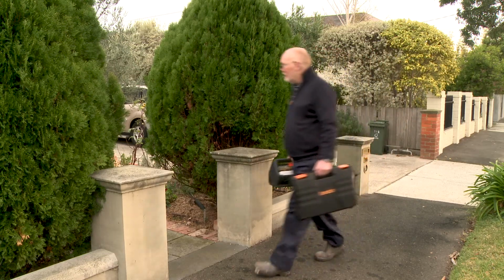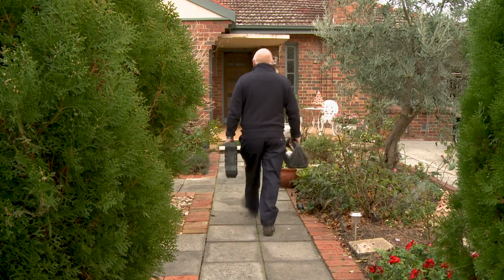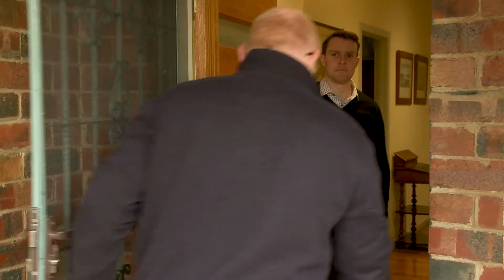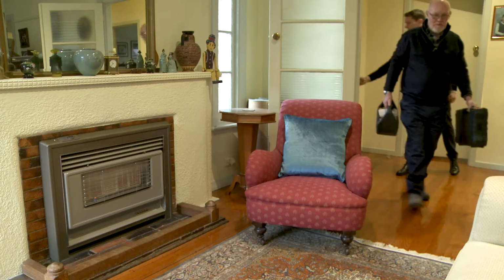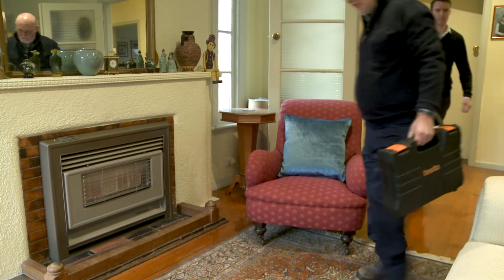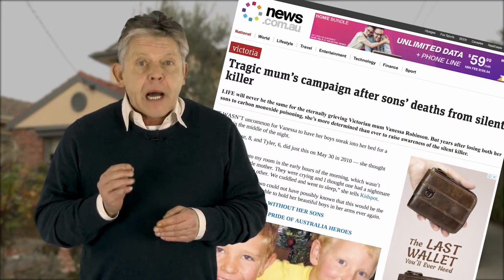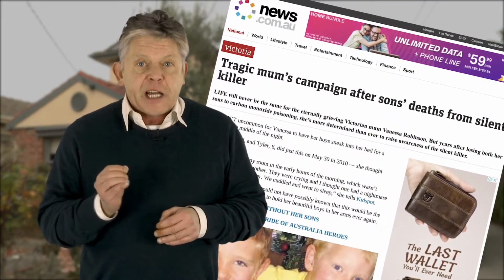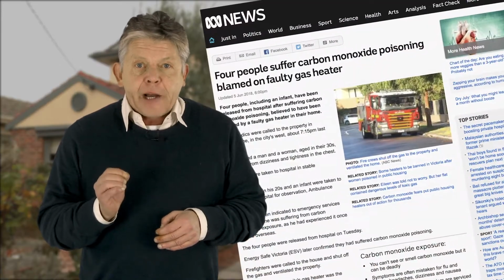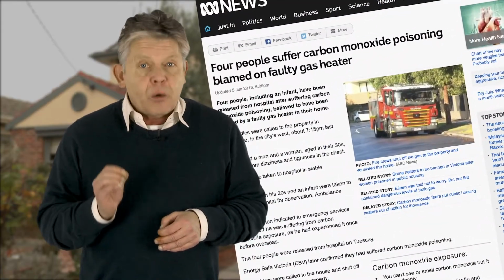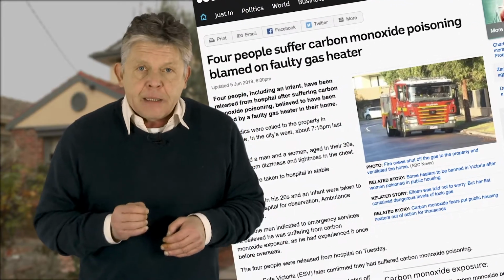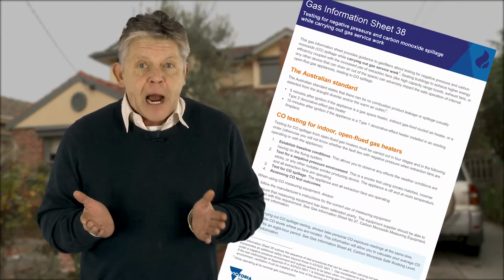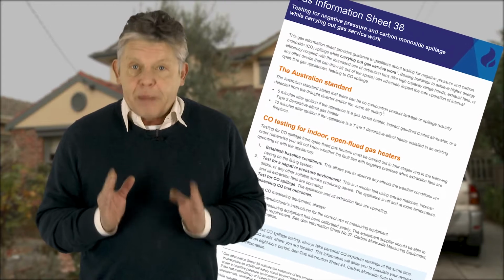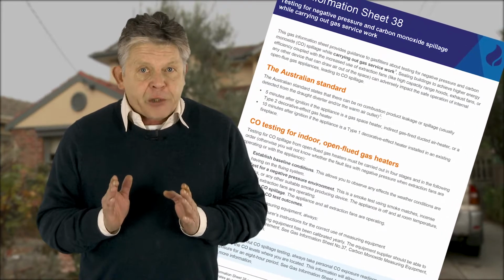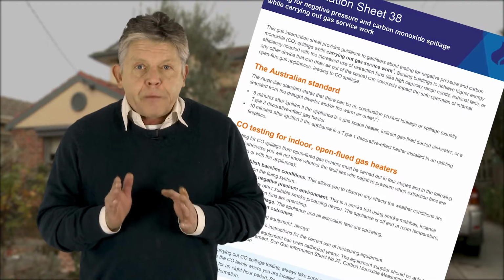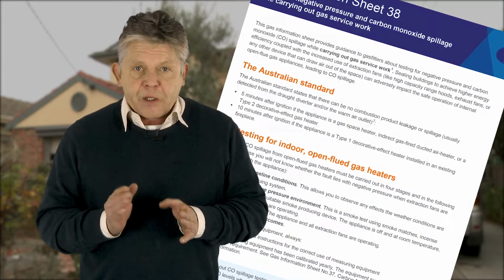To protect you and the public, the Victorian Building Authority has produced this short video to give an overview of carbon monoxide spillage testing for gas appliances. As you know, carbon monoxide or CO spillage testing must always be carried out when installing, servicing or repairing gas appliances. Updated testing procedures now in place take into account better sealed buildings and the negative pressure effect of modern, more powerful extraction fans and range hoods.